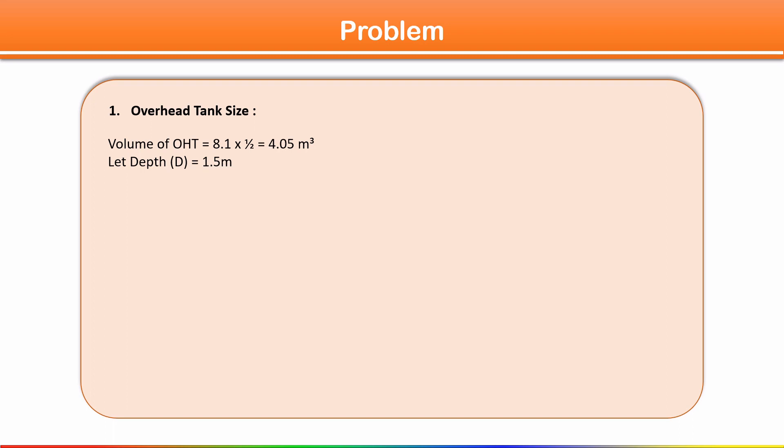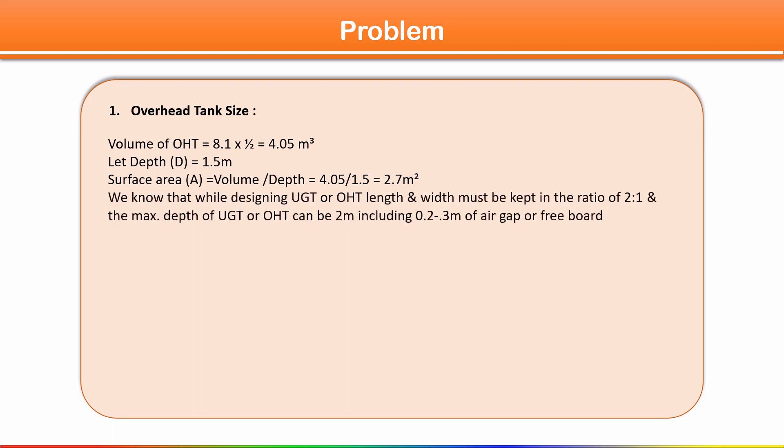Once we have the volume, we assume a depth. The maximum depth for OHT or UGT is 2 meters including freeboard of 0.2 to 0.3 meter. Let's take depth as 1.5 meters. Surface area = volume ÷ depth = 4.05 ÷ 1.5 = 2.7 square meters. Length and width must be kept in ratio 2:1.